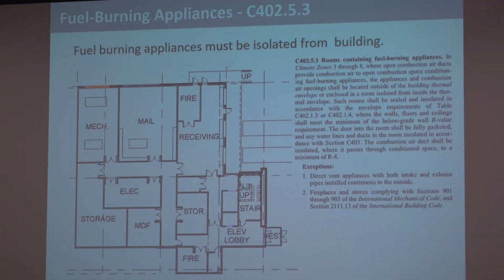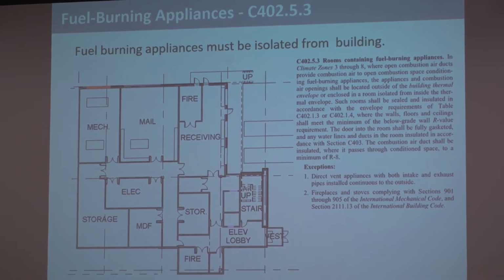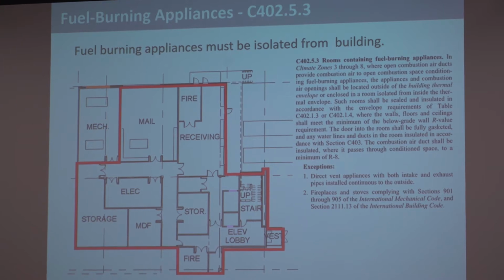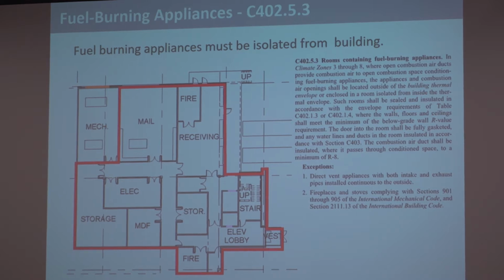If I've got a mechanical room here and I've got an appliance, and my mechanical engineer tells me, oh, I need to have a louver for outside air intake for that appliance. It's just for fresh air intake to make up air for that appliance. That entire room, that mechanical room, is now outside of your thermal envelope. That means the thermal envelope does not include that louvered room, and we're trying to get rid of that air leakage. I mean, this is sort of good practice, something that we've done for a long time. Now the code is recognizing that any room with a big outside air louver is outside the thermal envelope.